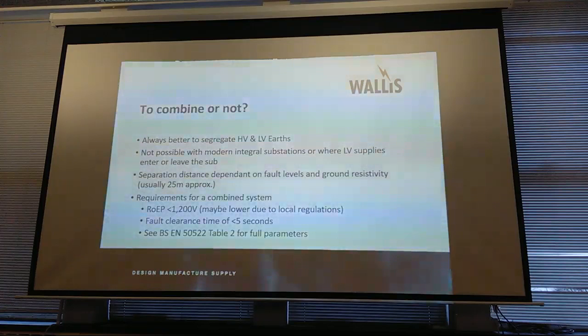To combine or not, HV and LV earths. It is always better to segregate HV and LV earths. But there are very, very few installations today where you can actually do that. Especially when you're taking an HV substation and building it into a student accommodation block, office block, hospital, whatever. That hospital, that student accommodation will be an LV environment. You have the rebar bonded to the lightning protection system. The lightning protection system is bonded to the LV network as part of the 18th edition wiring regs. You have to do it.